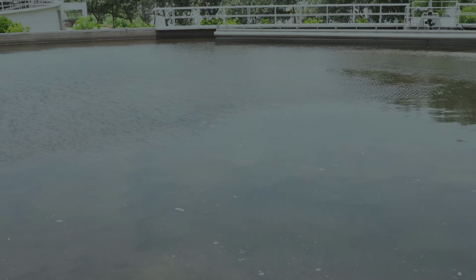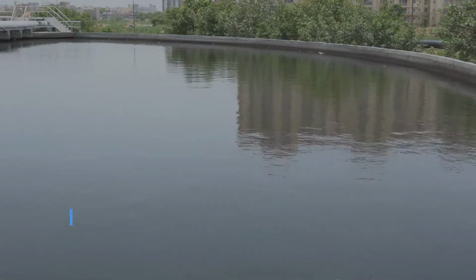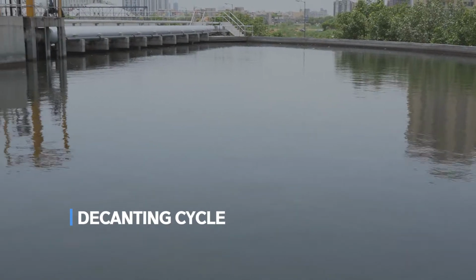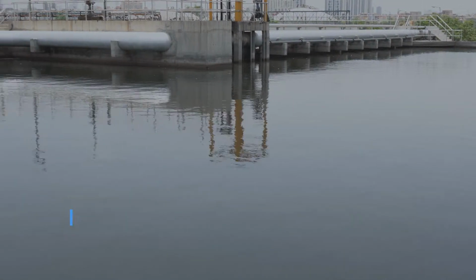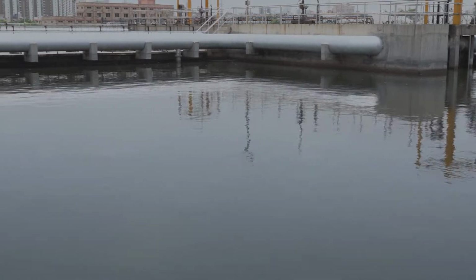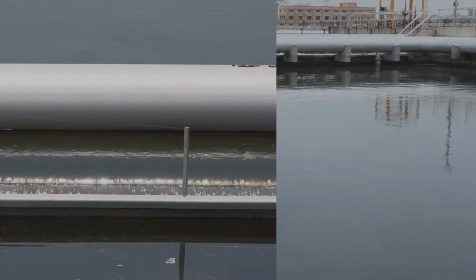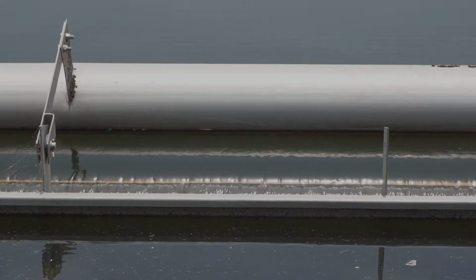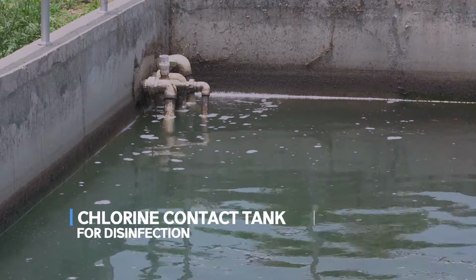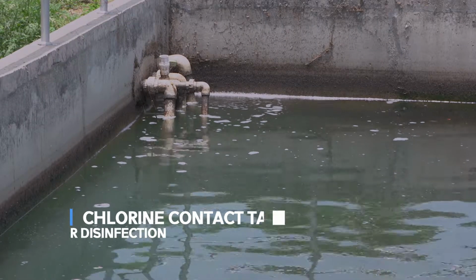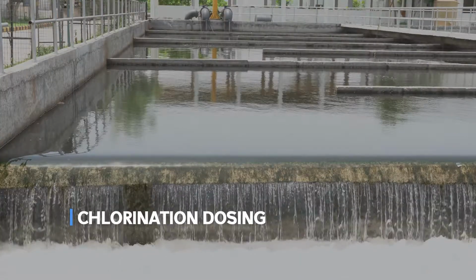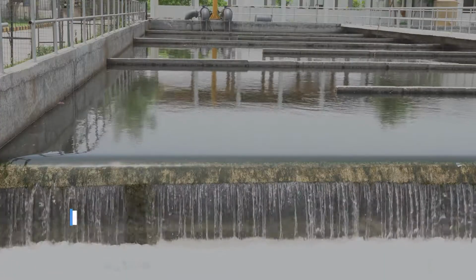In this cycle, all mixed SBR sludge is settled at the bottom of the SBR basin, and supernatant treated sewage remains up to the last level of the decanters. 63 minutes of decanting cycle is provided for treated sewage to flow from the SBR basin to the outlet of the tank until the decanting level of the SBR basin reaches 2 meters. The treated sewage from the C-Tech basins is further taken to the chlorine contact tank, CCT, for disinfection using chlorine dosing at a rate of 5 mg per liter.